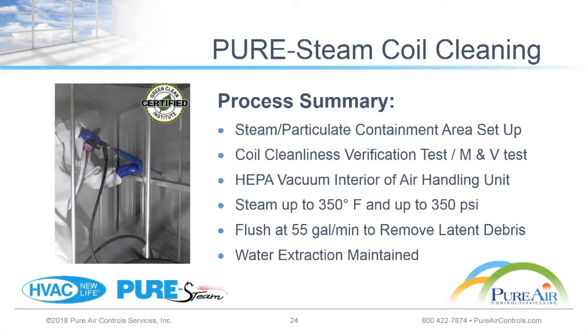Then before we actually even start the cleaning process, we take what's called a coil cleanliness verification test. This is a measurement and verification test where we traverse the coils with a fan. Now the unit's off - we're licensed mechanical contractors, so we work with the facility directors.